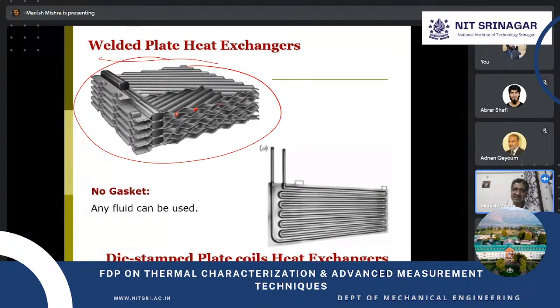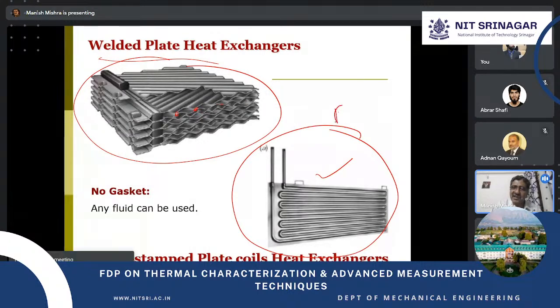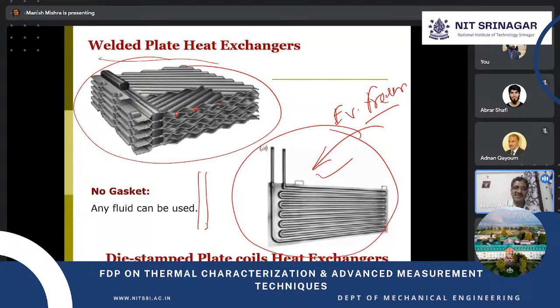This is the die-stamped plate coil heat exchanger. If you've seen slightly older refrigerators, the evaporating coil in the freezer compartment used this variety. It is two plates of aluminium brought together, with a die-stamped fluid passage in between through which the refrigerant flows.